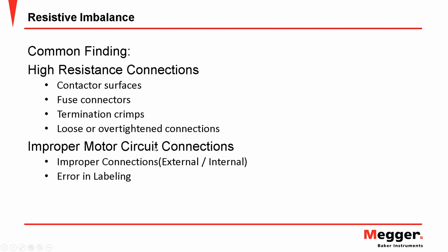Of course, it could also be caused by improper motor circuit connections. If you have a motor that came in from a manufacturer or a rewind facility that had been mislabeled or wasn't properly labeled or labeled at all, you could potentially hook up the leads improperly and not get the Y connected properly, as an example, and that would lead to imbalances as well. So that kind of testing on the front end will definitely help us out.